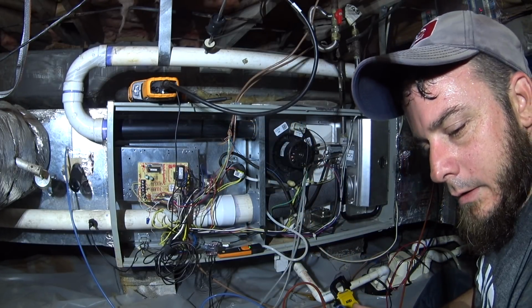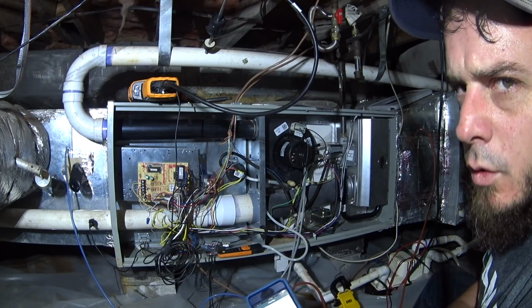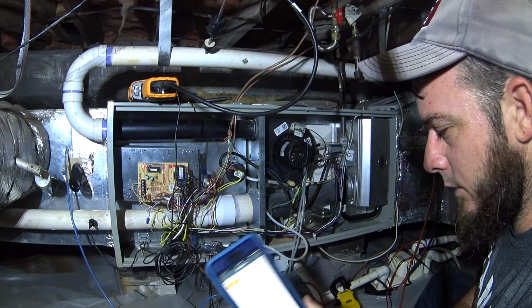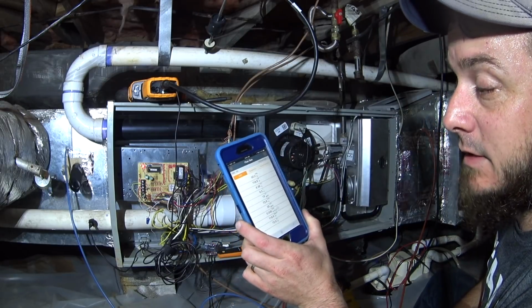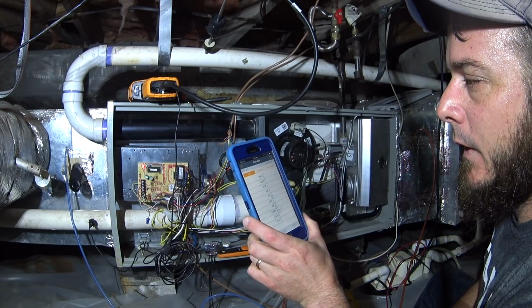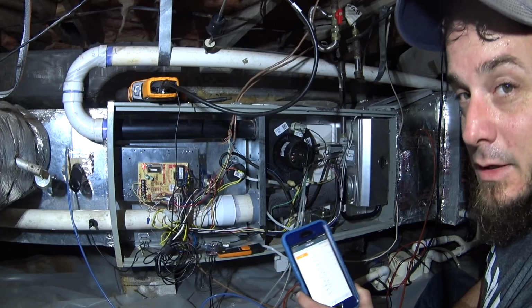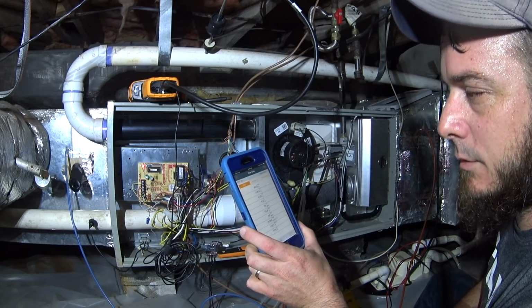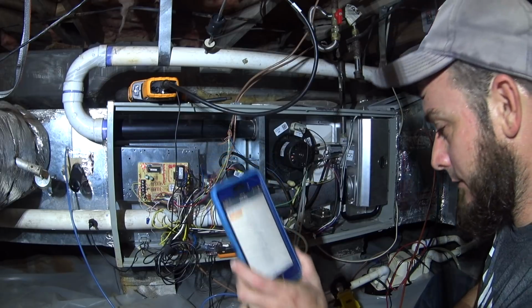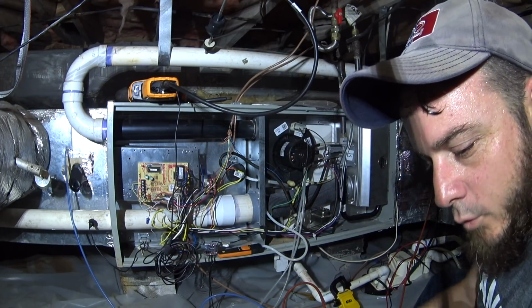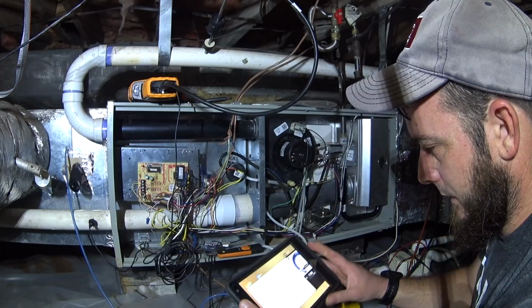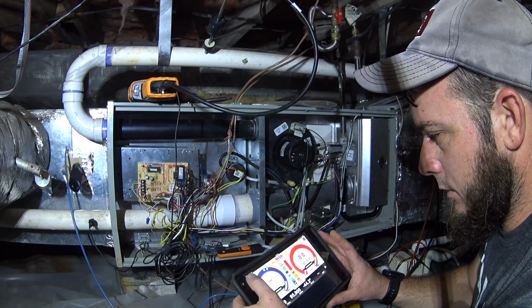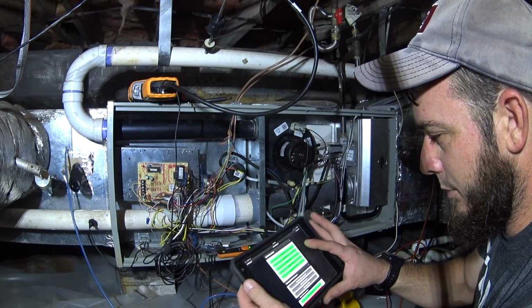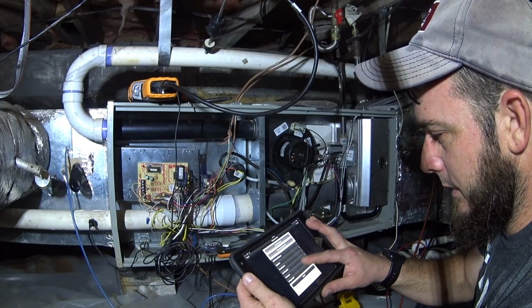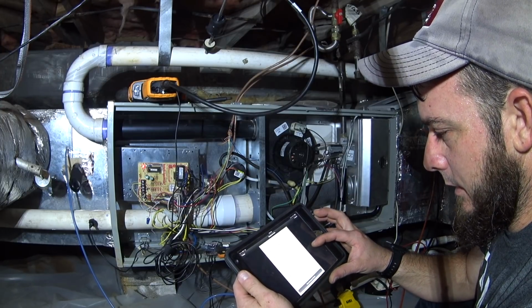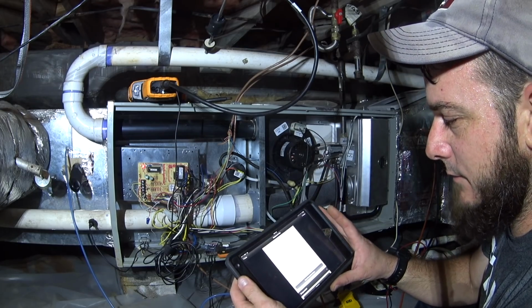If we had more gas pressure or slightly larger orifices, we could get excess air down just a little bit. But at maximum recommended gas pressure, you'd have to do some modification to get more out of it. Right now we are getting a 44 degree temperature rise. It's not necessarily slowly creeping up, but it is still balancing. And the allowable temperature rise is 35 to 65.